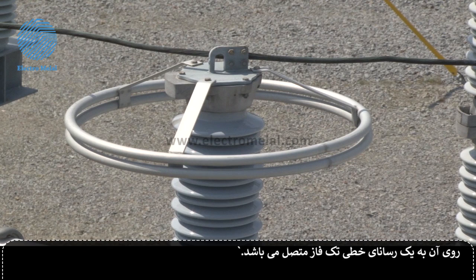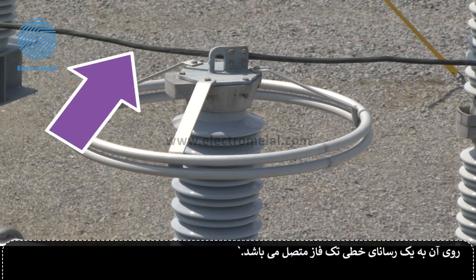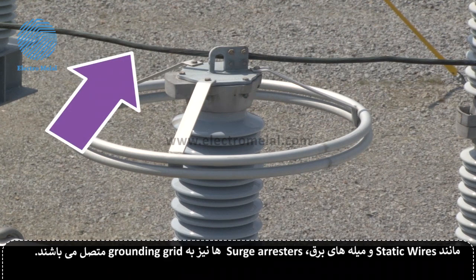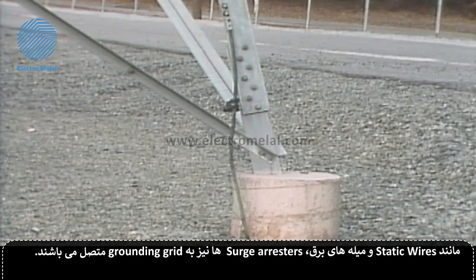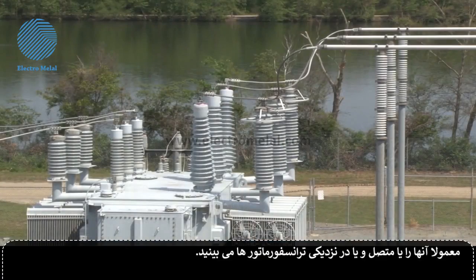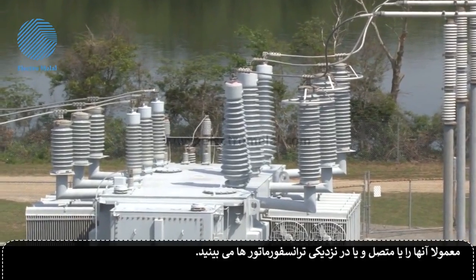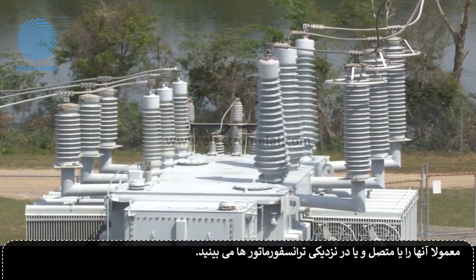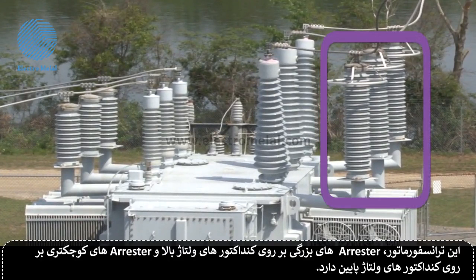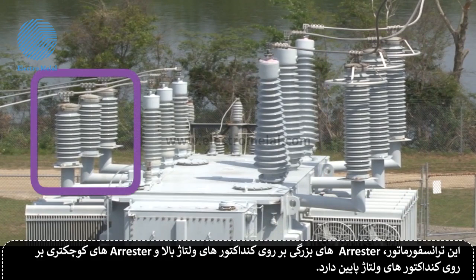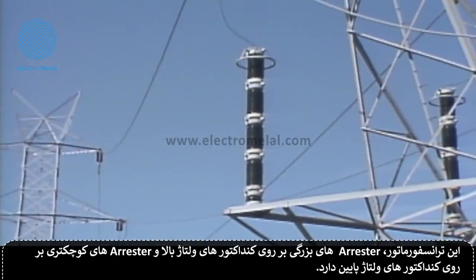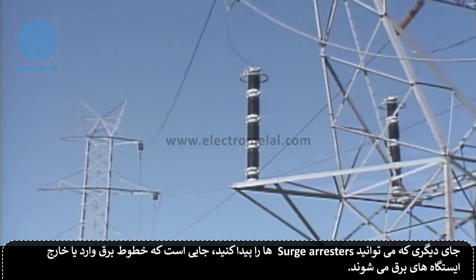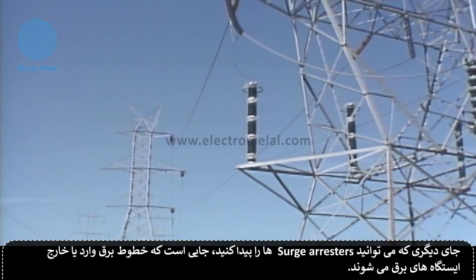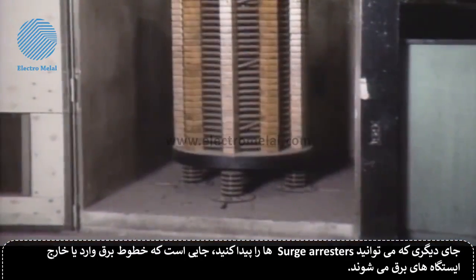The top of an arrestor is connected to a single-phase line conductor. Like static wires and lightning rods, surge arrestors are connected to the grounding grid. Usually, you'll see surge arrestors installed on or near power transformers. This transformer has large arrestors on its higher voltage conductors and smaller arrestors on its lower voltage conductors. Another place you can often find surge arrestors is where power lines enter and leave the substation.